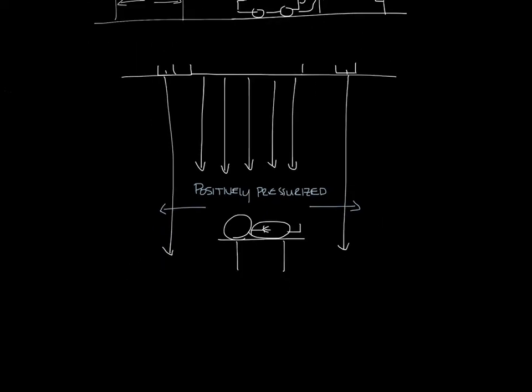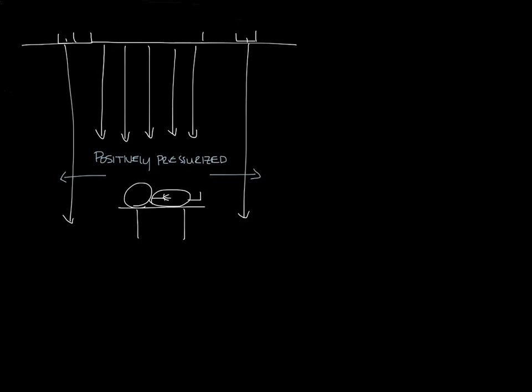You also want the operating room to be kept positive relative to adjacent areas. Put the floor down here. And let's say there's a door over here somewhere. So you want the operating room side to be positive, the outside hall to be negative, so that the airflow wants to move from the positive side in the operating room out into the hall.